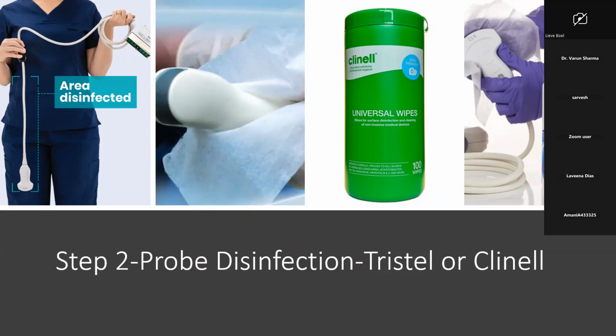The other thing that's used now is Tristel. Tristel is a wipe that kills sporicidal, fungal, bacterial, and has good virucidal effect. It has 3 wipes. One wipe is specifically designed for ultrasound machines, and doesn't damage the probe. But more importantly, it will kill everything. I don't know how well Clinell will kill fungus and viruses, but that's what we use. Tristel will kill everything. Tristel is quite expensive.